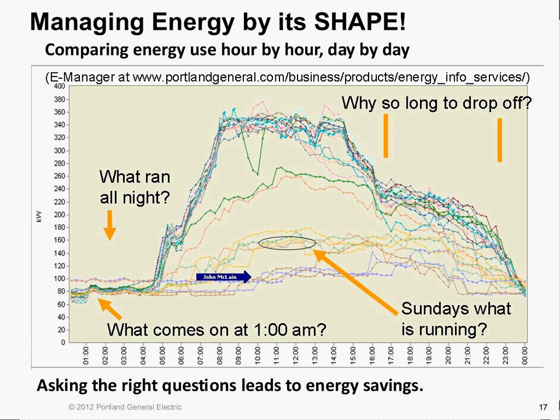I like the question, what comes on at 1 a.m. every night and stays on until everybody starts coming in. For a while, this was a mystery. Back to the CSI school district person, and found that the IT department was turning on every computer in the facility and backing them up, but the software that turned on the computers automatically couldn't turn them off.